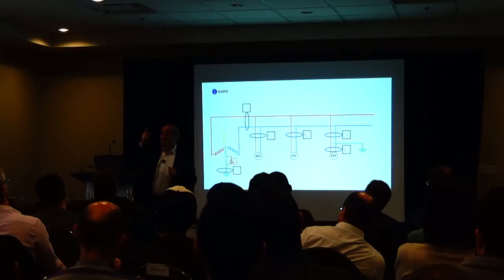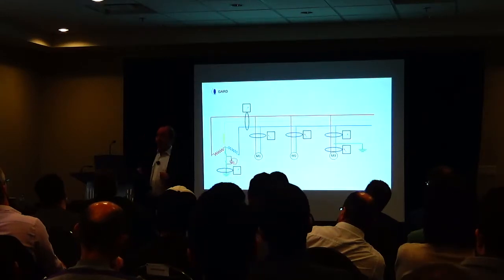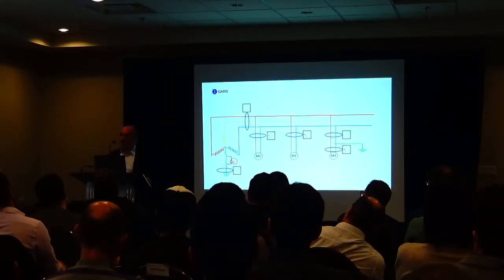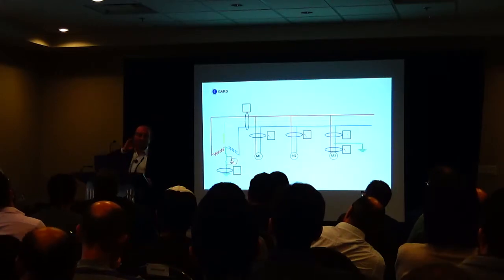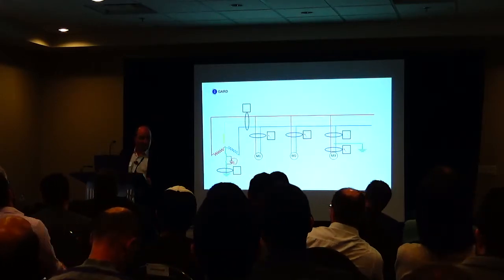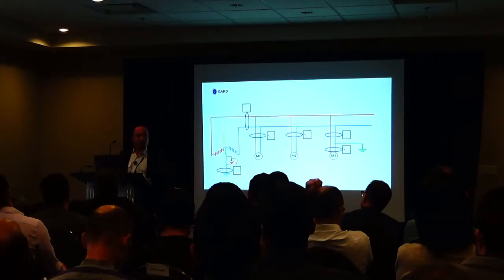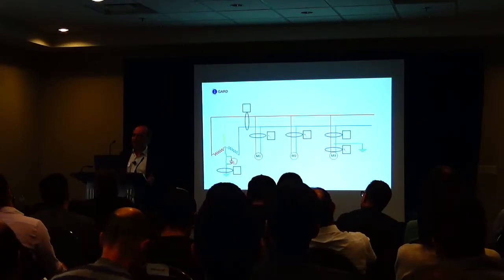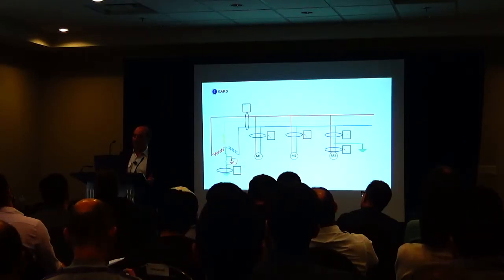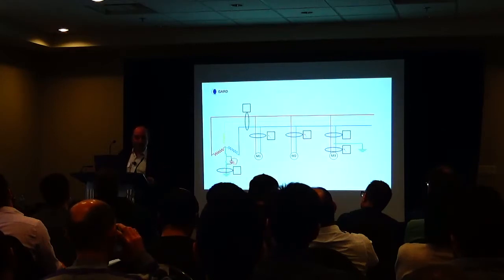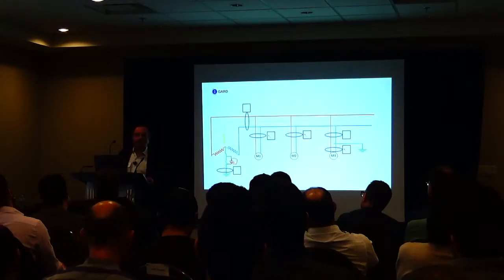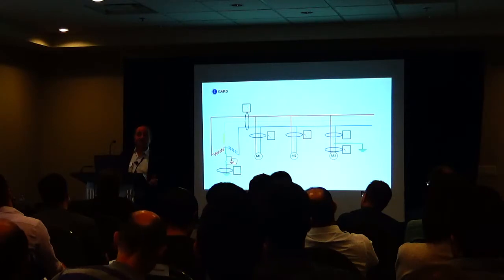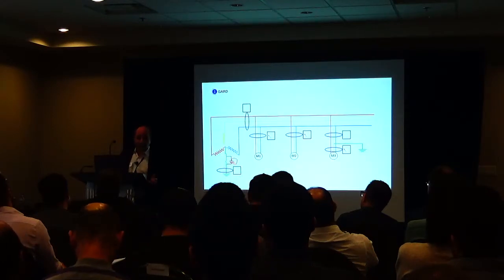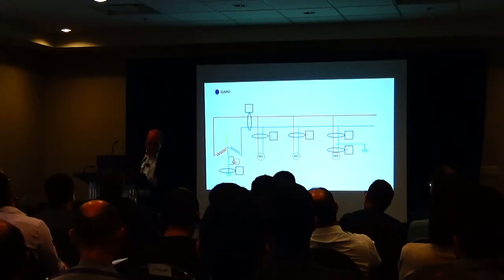And it's connected to A phase, right? He locks it out, tags it out. It's confirmed de-energized, right? So now he's going up to change the ballast. Does he take his gloves off? He could take his gloves off. It's allowed, right? He may want to use his gloves on because he doesn't want to get his hands dirty, but he can take his gloves off.